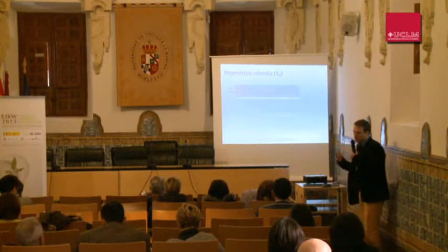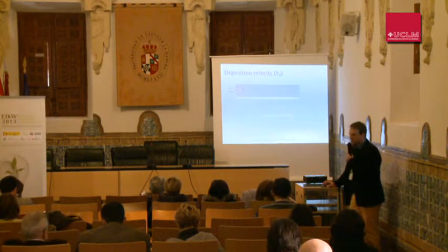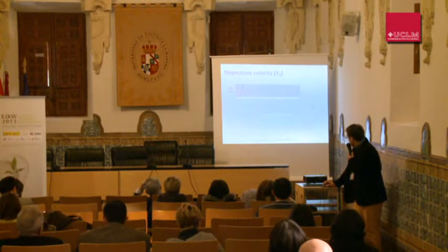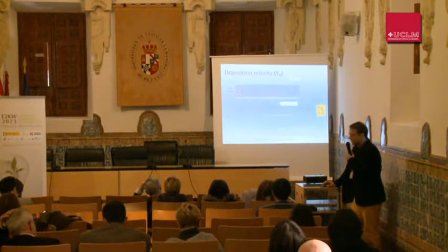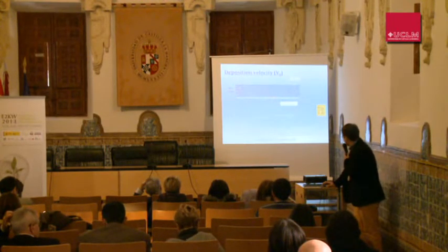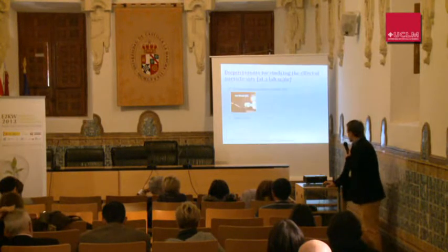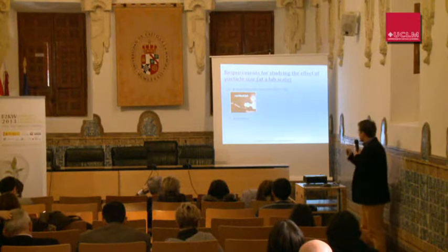we used an experimental way of measuring the deposition velocity. This diagram shows a duct with airflow and particles. Here they are yellow because we used fluorescent material. So they are particles in the bulk of air. And the deposition velocity could be expressed as the mass deposited on surface divided by the mean concentration of particles in the bulk air. That's what we did in this study. We challenged this experimental way to measure the deposition velocity, but in a circular duct by considering different orientations. I will talk a little bit more about that later.